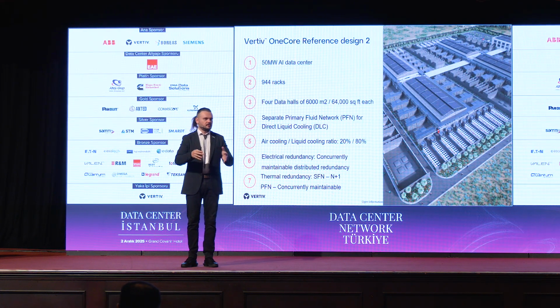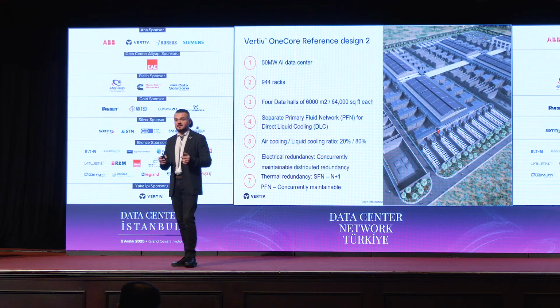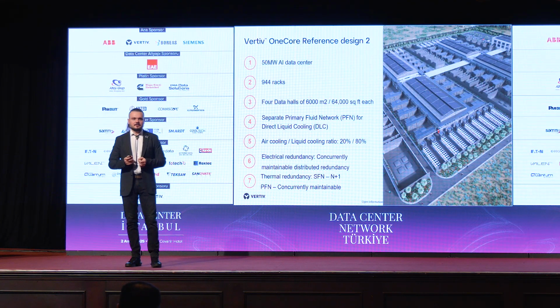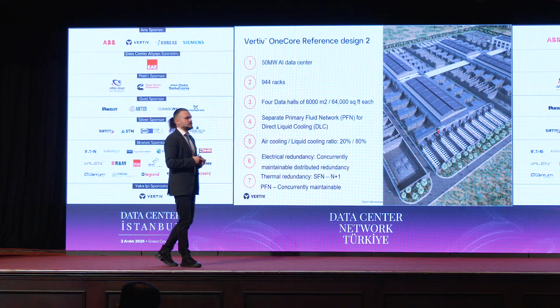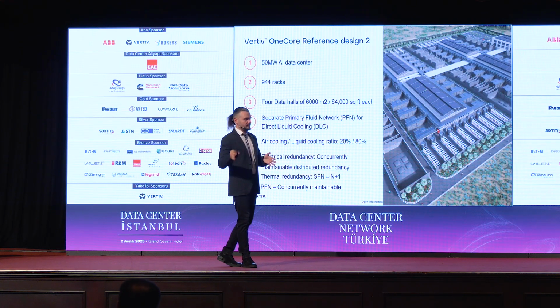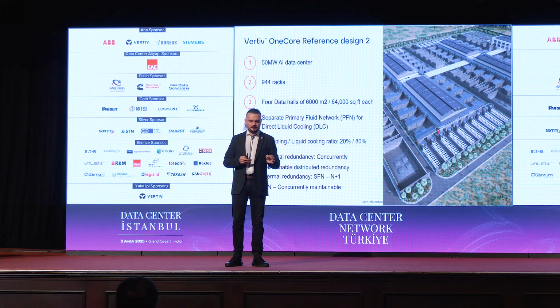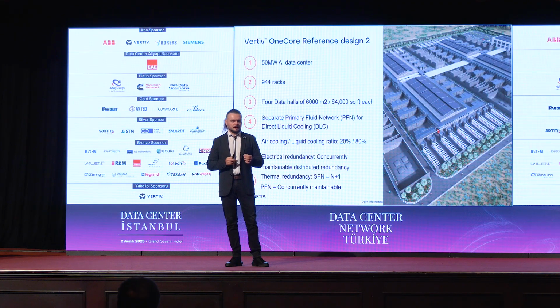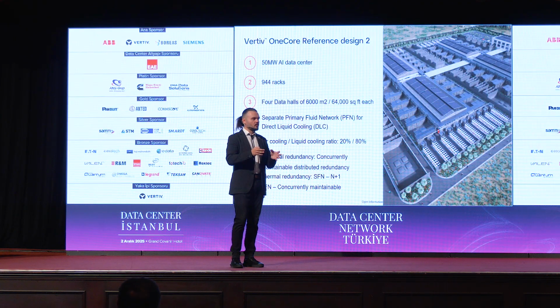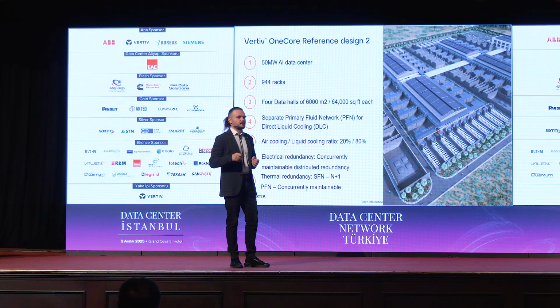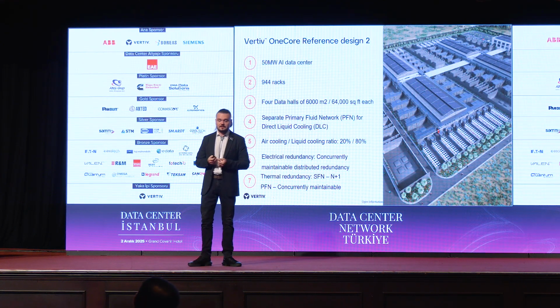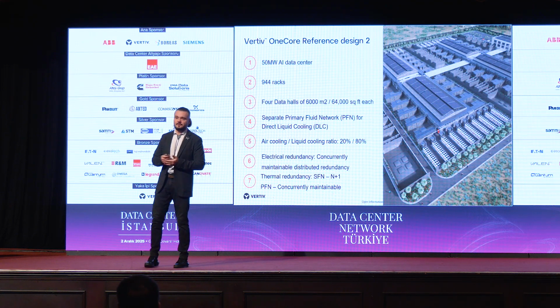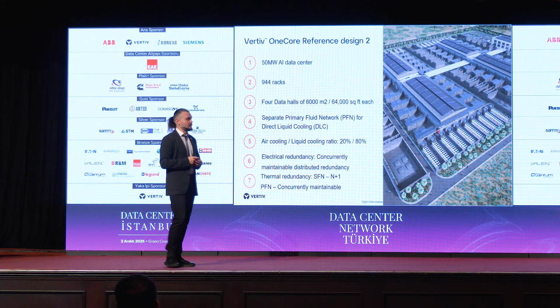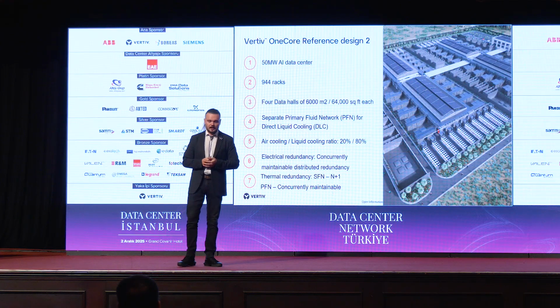Nothing critical there because the superpod is quite a dense environment. But another limitation is 500 meters from the core to the leaf. So from the network rack inside the core part to every server rack in the superpods, you should not exceed 500 meters, and this gives some challenges when we're talking about 50 megawatt, 100 megawatt, and bigger data centers.